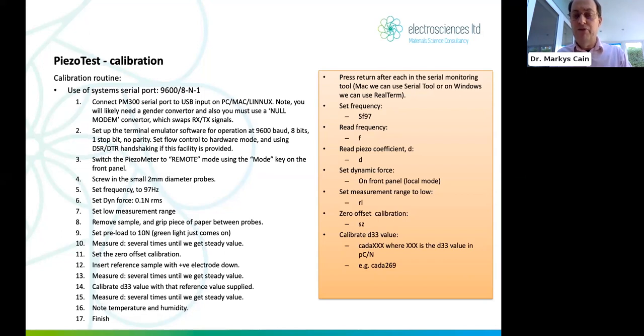You need a serial port to read in and to write back to the Piezotest machine. So this is a load of detail here, okay? Now, depending on what computer you have, if you have a Mac, you can use something called Serial Tool. In Windows, you can use something called RealTerm. This allows it to emulate a serial port, okay? And these are the sorts of things in the colored box there on the right-hand side of your screen. You can see, to set frequency, use S for set, F for frequency, 97. To read frequency, you just type F and return. To read the D coefficient, you just type D and return, and so on and so forth. And there's like a dozen or two dozen parameters that you can read and you can set. And there are issues with regard to setting calibration that I'll go into in a moment or two.